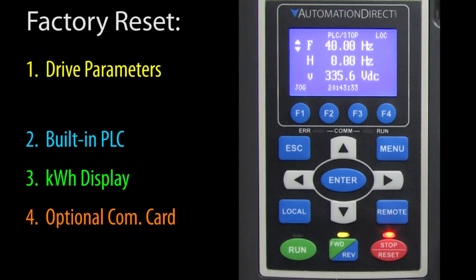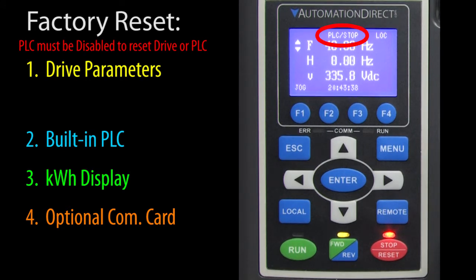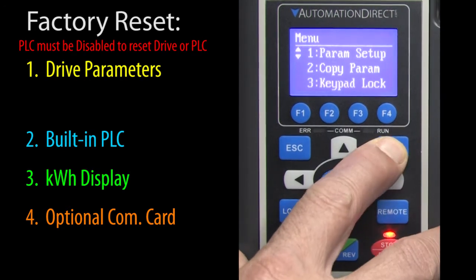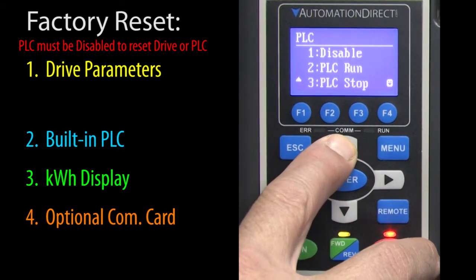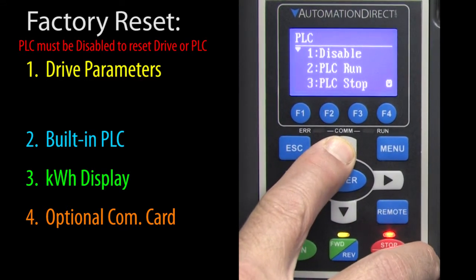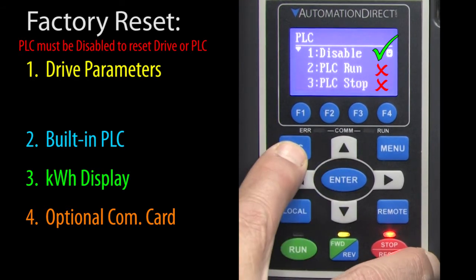Before resetting the drive or the PLC, make sure the PLC is disabled — you don't want it trying to control the drive while resetting, and you can't reset the PLC while it's active. You'll see the PLC status on the main screen if it's enabled. If it is, go to the main menu, item 4, select disable, and press enter. The PLC can't be in either run or stop mode to be reset — it has to be disabled entirely.